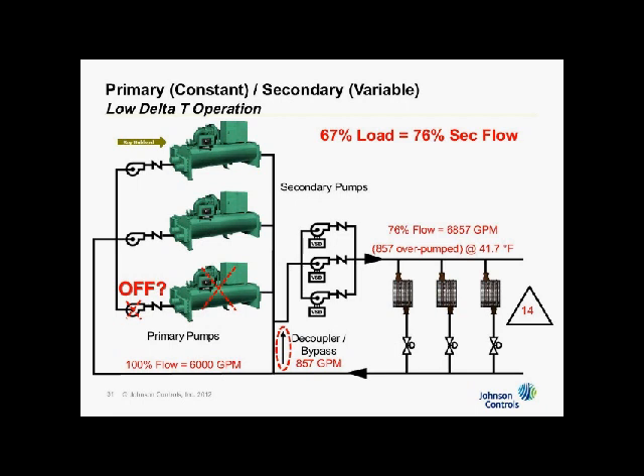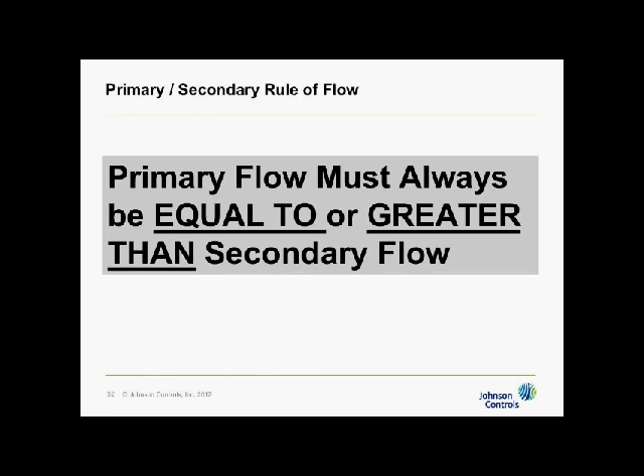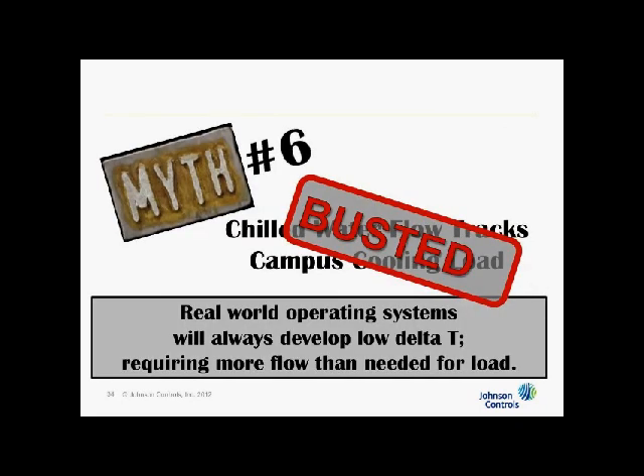So there's a couple of problems that happen there. But this is rule number one about primary-secondary. You must keep the primary flow equal or greater than the secondary. It must always be that way or the system won't work. And that forces us to run more chillers than we need. It forces that we can't load up chillers. That's the negative impact of low delta T. All right. Now, here's another. So what we've done is we've busted that myth that flow tracks load. In real-world operating conditions, you'll always develop some sort of low delta T, so flow does not track load. Okay?